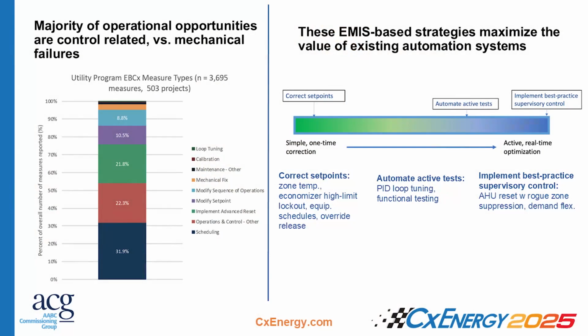So from the moment that the fault is detected, the work order gets submitted, and then finally the controls contractor or the controls tech has some time to go to the building automation system and finally clear that fault out. It can take quite a bit of time, and throughout that time there's energy being wasted that could have potentially been solved at the moment that that fault was detected, right? So we've done some fault prevalence studies over the past few years, and we actually found that the majority of the faults that exist within buildings are controls faults.